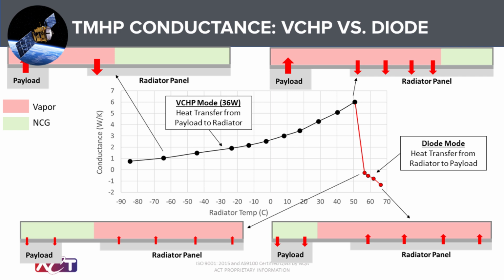So now when you go on the bottom, we reverse the gradient. For a certain radiator panel, let's say the first point at 55 degrees C, the front, this is the temperature of the radiator. Of course, the non-condensable gas reservoir is at the left, and the front is somewhere in the adiabatic section. Obviously, vapor does not have access to the evaporator. If we go higher in radiator temperature, the front is pushed more to the left because vapor pressure obviously increases, and we know it increases fast. We are already on a very steep vapor pressure portion. So the conductance increases. When I say conductance, it's parasitic conductance.